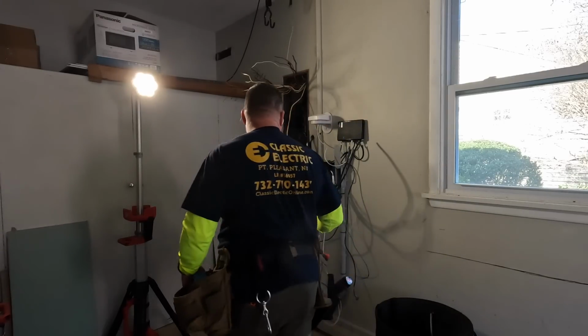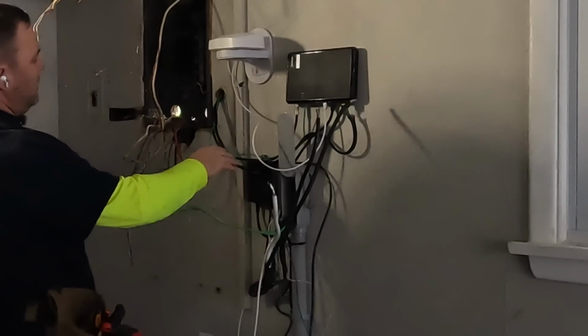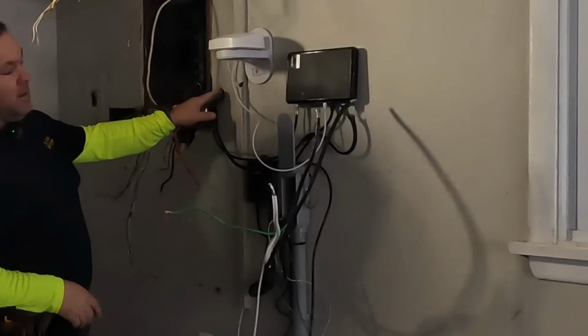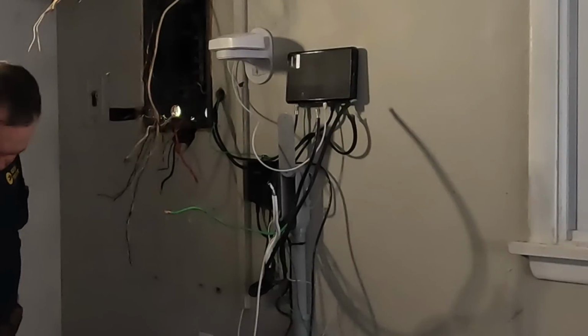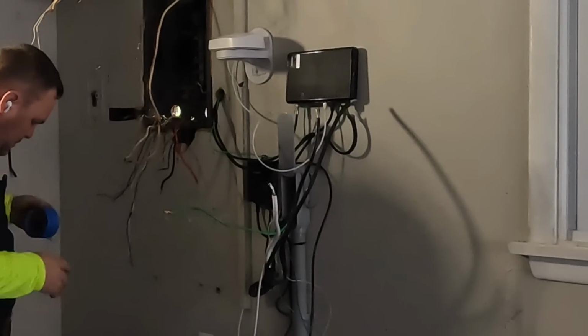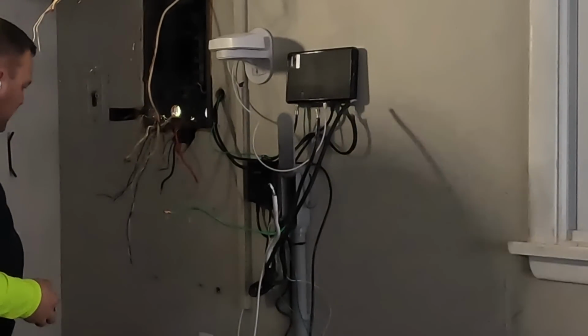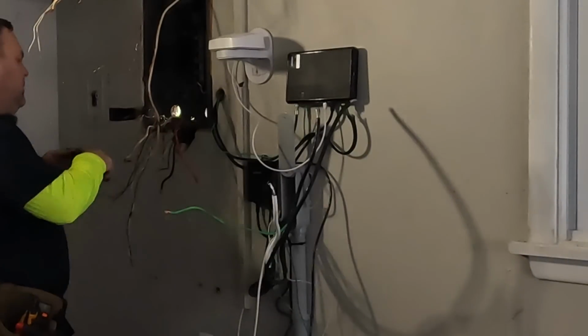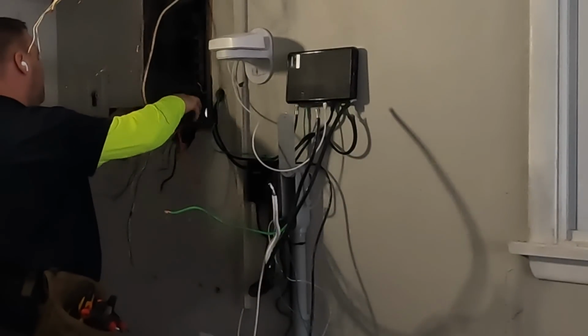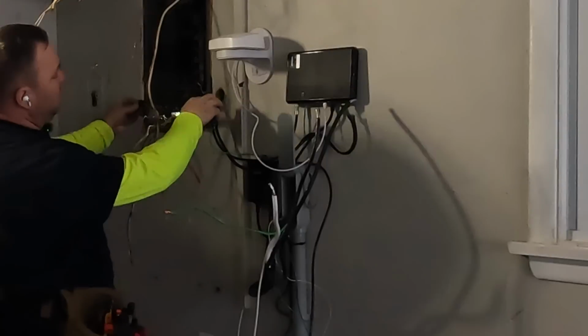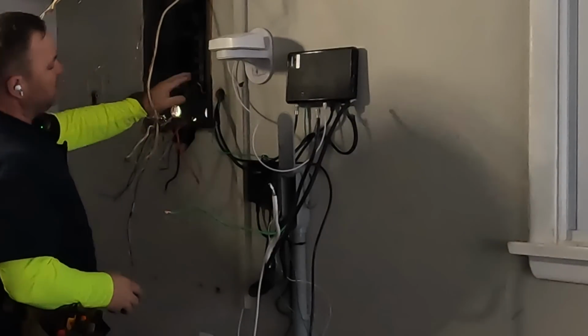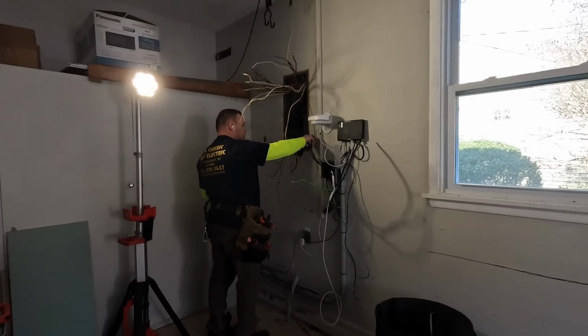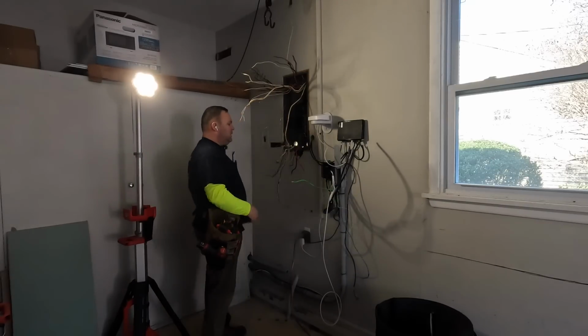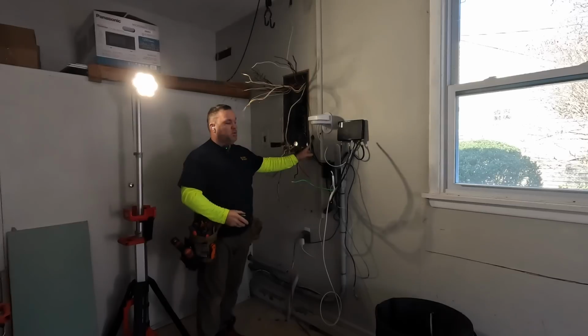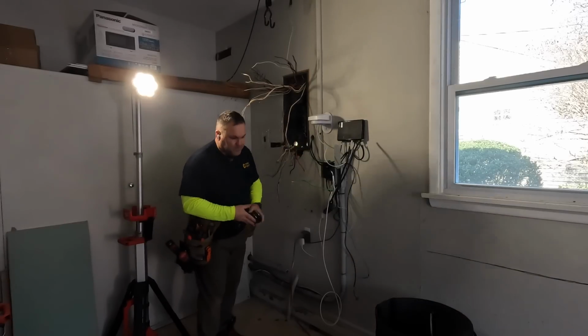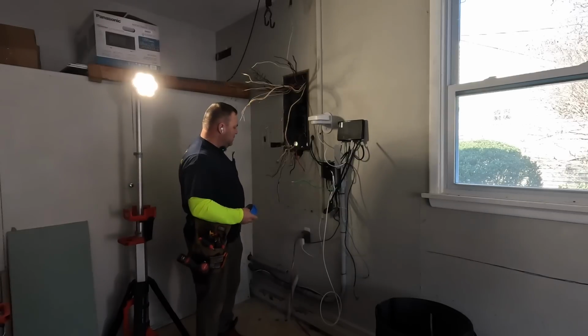As you can see, we've relocated the telephone equipment. When they drilled this, they drilled right through the stud right here. So my main concern here was, do I have 14.5 inches for the new panel between stud bays here? So I can see the stud bays open here. If you measure 14.5 over, it's right there, and this is where they drilled through. So my biggest concern now is that the panel cover is going to fit on there without moving this over. If I have to notch away some of the sheetrock, I will. But for the time being, we're going to leave the telephone equipment right where it is and hope it doesn't affect us going forward.